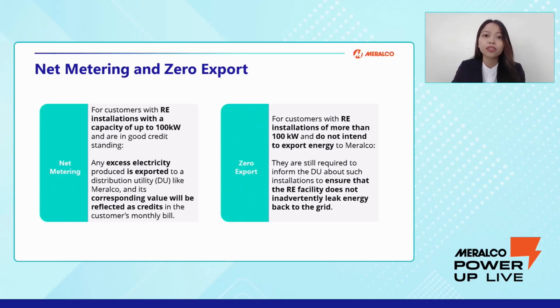But why are we doing net metering? Under net metering, your regular meter will be replaced with a net meter. This allows us to capture actual consumption of the customer versus the excess electricity generated by their RE facility, which is being exported to the grid. Then that excess electricity will be credited to your bills and essentially becomes your savings. However, without net metering, this excess electricity may even be read by your regular meter as an added consumption and may also add to your bill. So, it is best to inform Meralco if you are planning to have a solar panel installation.